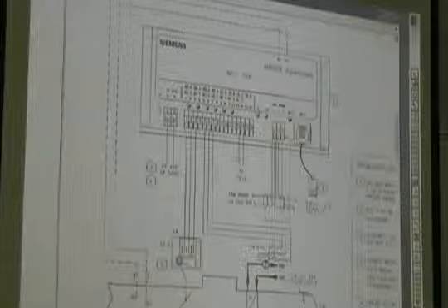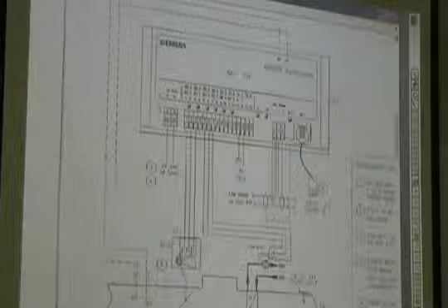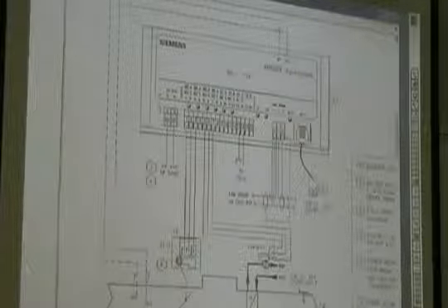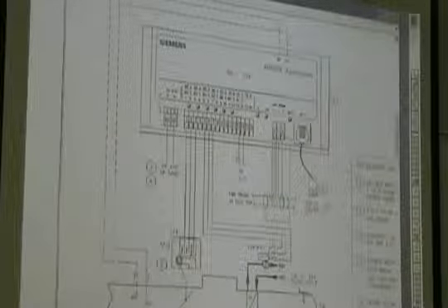Okay. So the little valve actuator is the same way. It does the exact same thing. And when the TDC calibrates, it runs it back to 0 also. Since you asked that, when we have rooms where we cannot close that damper because of airflow requirements, and we install what we call auto zero modules, at that point we never zero this actuator again. So after 6 months in operation, it may be a little lost. It says it's wide open, but it's not. Okay? So they've come up with a sequence in here on how to adjust for that. Basically all it does is look at the airflow. It says if I'm not at full airflow, but my damper is wide open, it just arbitrarily drives that motor in the open direction for like another 10 seconds, trying to get it wide open.